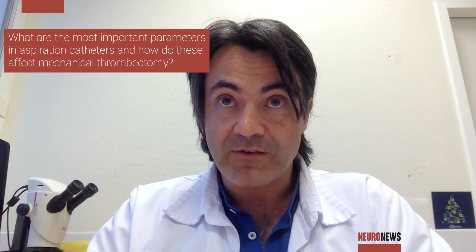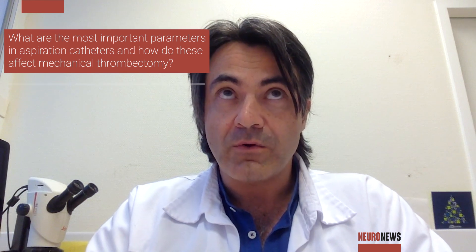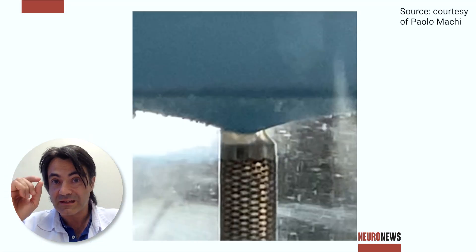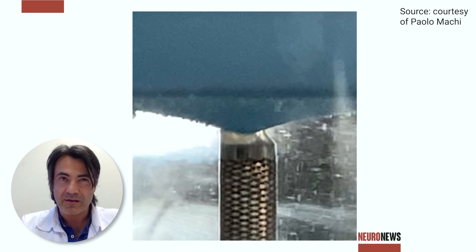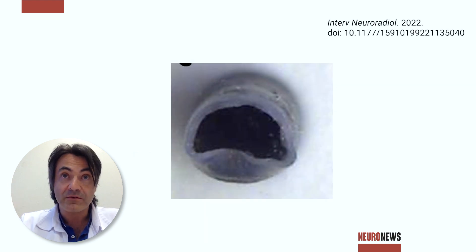Flow rate and aspirational force are related to specific parameters, primarily the diameter of the device and also the behavior of the catheter. We have cases in which the distal tip of the catheter collapses under aspiration, which reduces the diameter of the distal tip, and so with the reduced diameter we also have reduction of the flow rate and aspiration force.